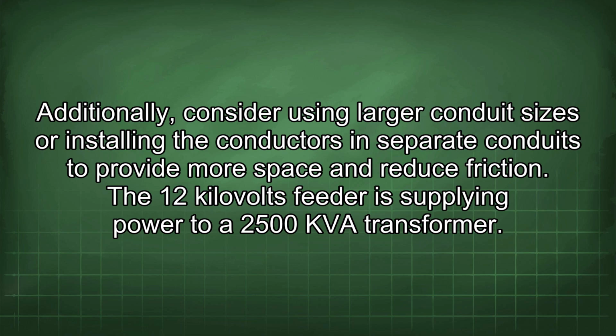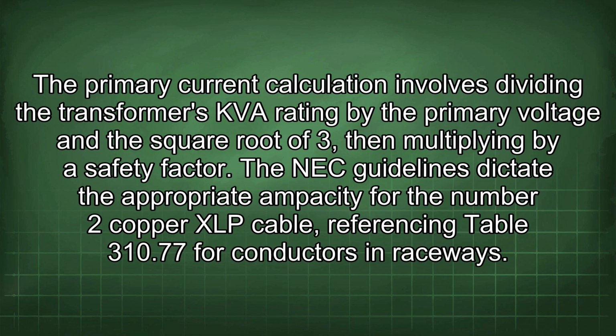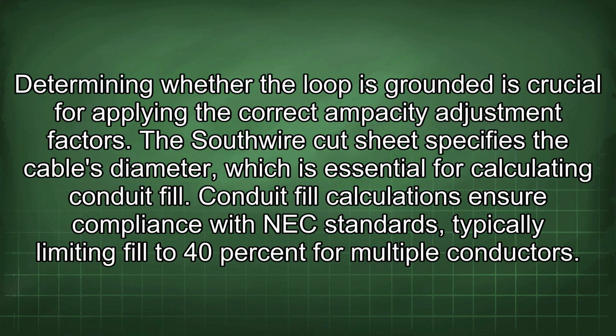The 12 kV feeder is supplying power to a 2500 kVA transformer. The primary current calculation involves dividing the transformer's kVA rating by the primary voltage and the square root of 3, then multiplying by a safety factor. The NEC guidelines dictate the appropriate ampacity for the number 2 copper XLP cable, referencing Table 310.77 for conductors in raceways. Determining whether the loop is grounded is crucial for applying the correct ampacity adjustment factors. The cut sheet specifies the cable's diameter, which is essential for calculating conduit fill.